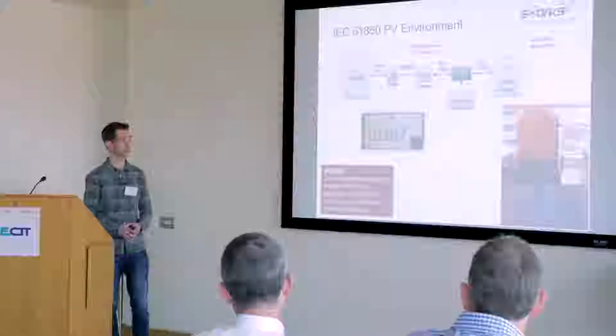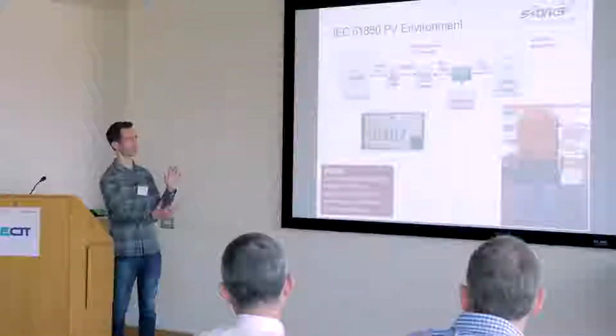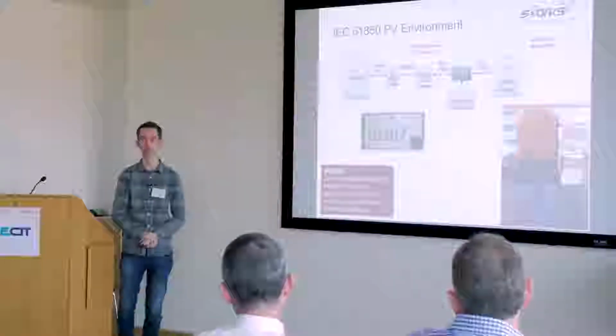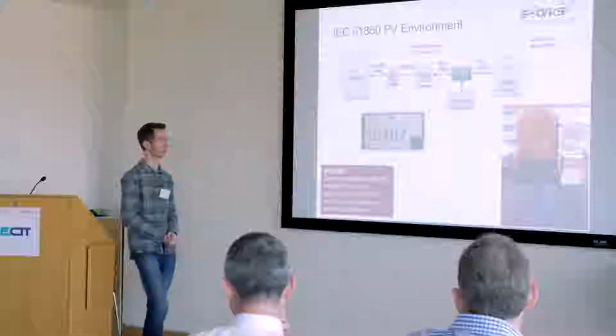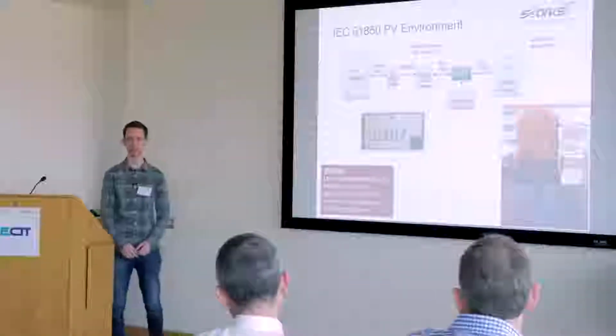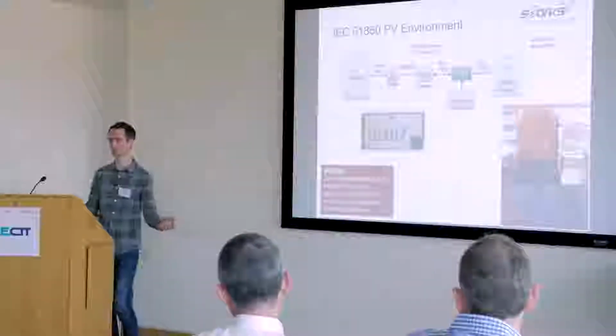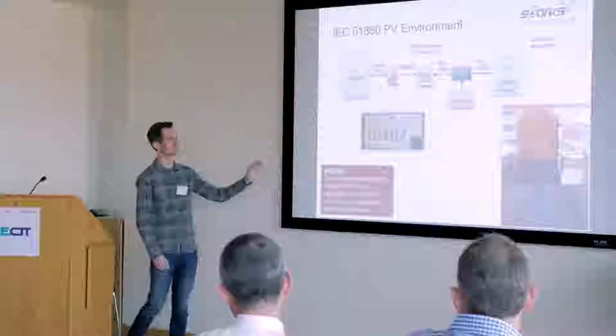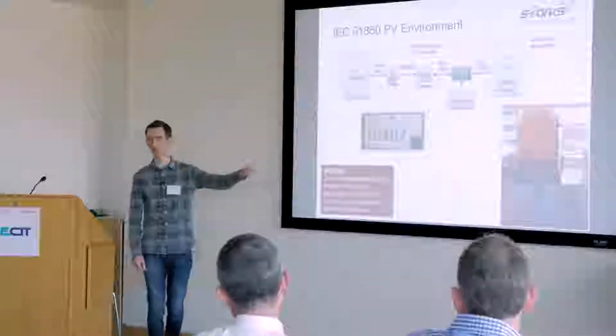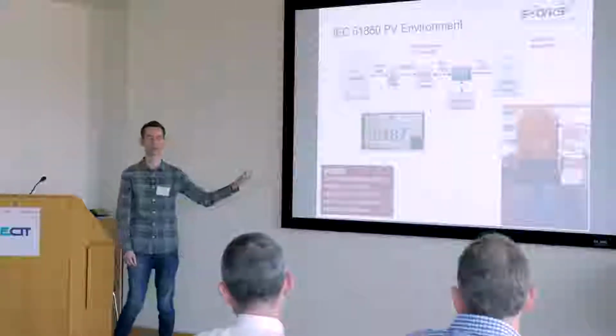This is a brief snapshot of what the PV testbed looks like at AIT. We'll start off talking about the protocol we're using. IEC 61850 is a large, all-encompassing protocol, kind of a silver bullet that solves everyone's problems. We're looking at a specific part of it, the MMS protocol, which is used here to provide communications between a gateway to the inverter and the SCADA system, the HMI that controls certain functions of the PV inverter.